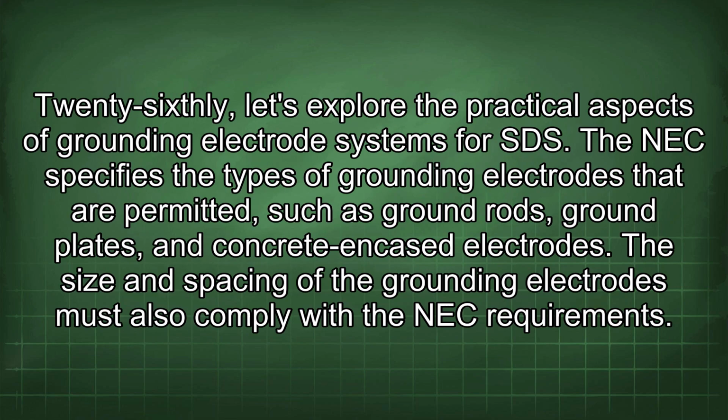26thly, let's explore the practical aspects of grounding electrode systems for SDS. The NEC specifies the types of grounding electrodes that are permitted, such as ground rods, ground plates, and concrete-encased electrodes. The size and spacing of the grounding electrodes must also comply with the NEC requirements.